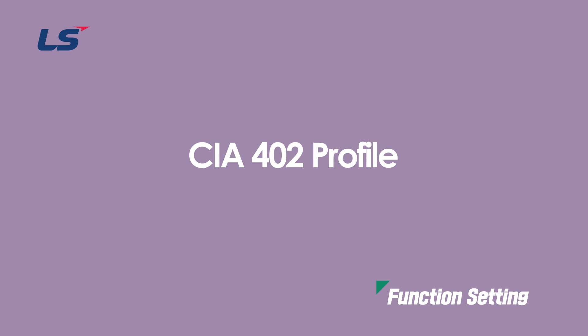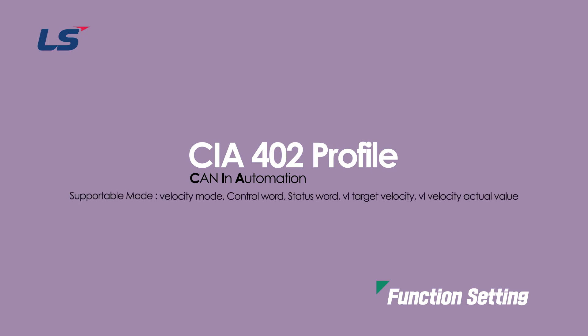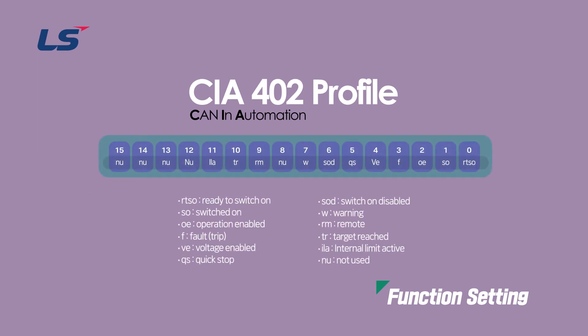In CIA 402 profile, CIA is an abbreviation for CAN-IN Automation, and only velocity mode is supported here. It is fixed as control word, status word, vl target velocity, and vl velocity actual value. Since information is assigned to each bit, please check the relevant bit information when communicating.